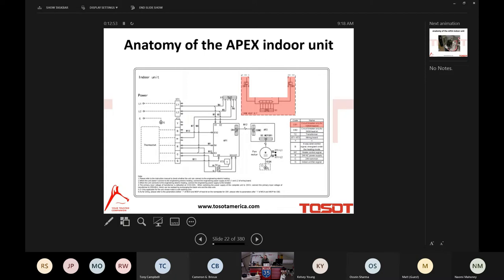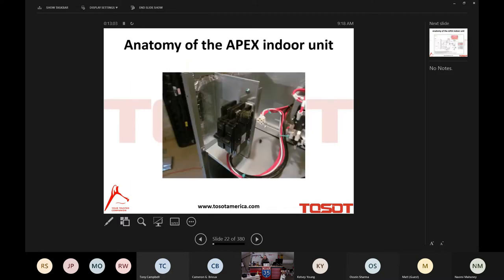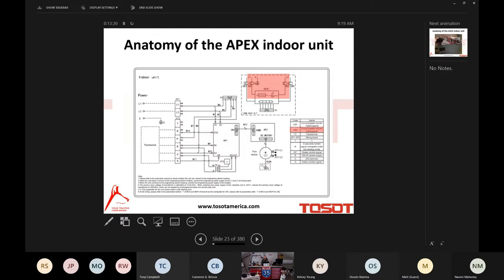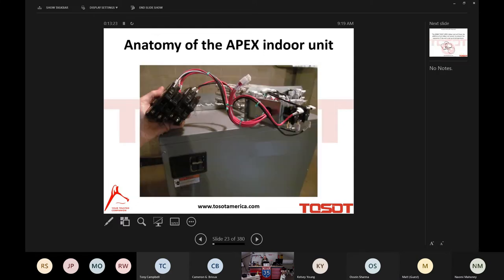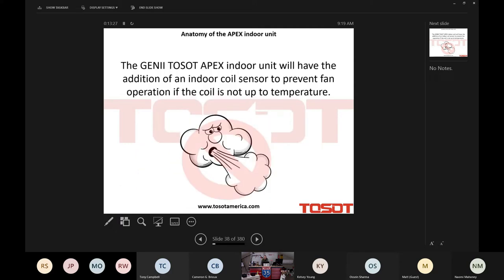But getting back to the point with the electric strip with the Apex, if you utilize it, you bring your 208/230 volt power source to the breakers of the electric heater kit. The 8 kW and the 10 have one breaker, as you see there. The 15 and the 20 have two. And again, I'll show you this in great detail as we move forward. Here's the 15 and the 20 with the two all factory supplied and wired breakers.